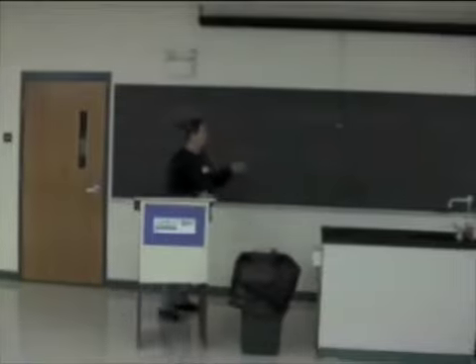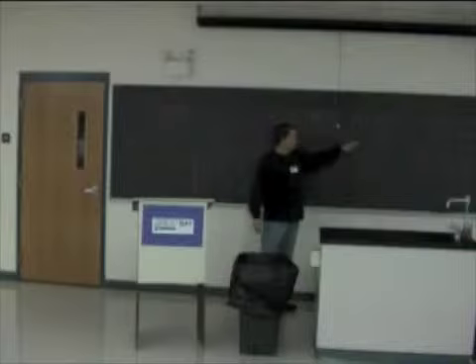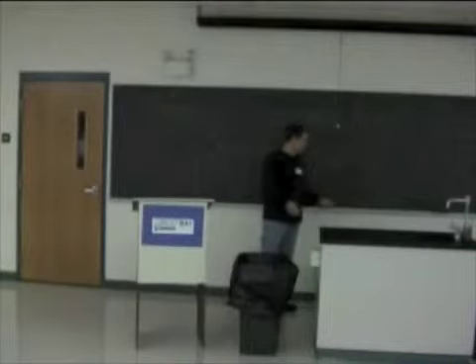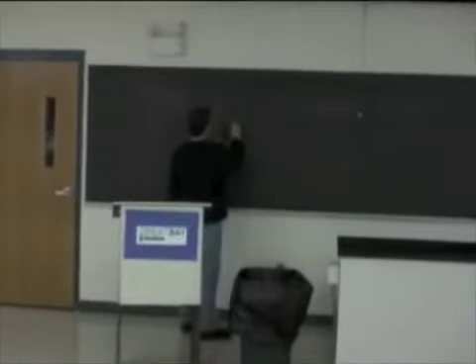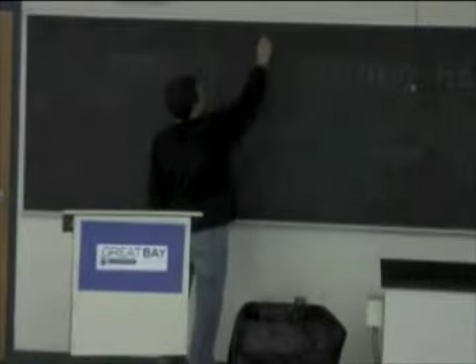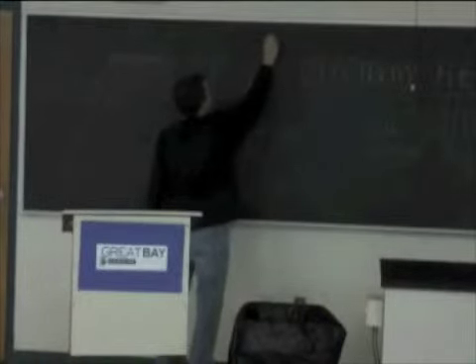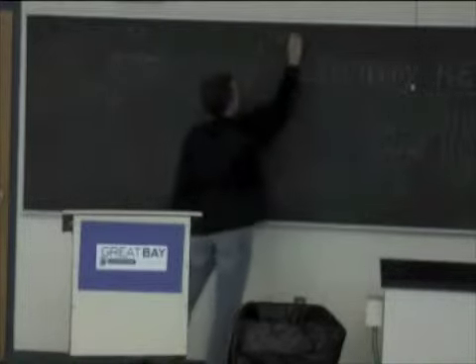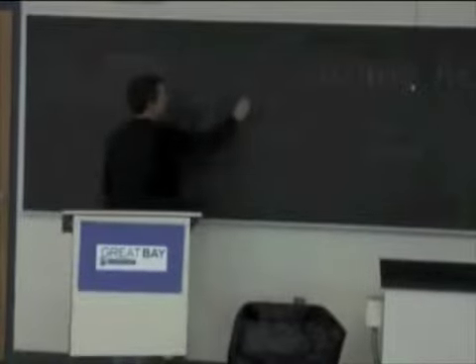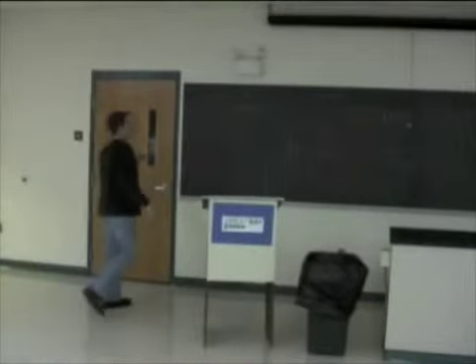And the funniest part about this, you can do this kind of stuff by behavior. We looked at a power curve for the high school, 1 day, and it goes along, and then at about 6 o'clock it goes from 180 to about 1,200 kilowatts in the course of 15 minutes. And what happens in that time? Everybody gets there and turns on the lights and turns on the computers and opens the refrigerators and turns on the coffee makers, and everything fires on at the same time.